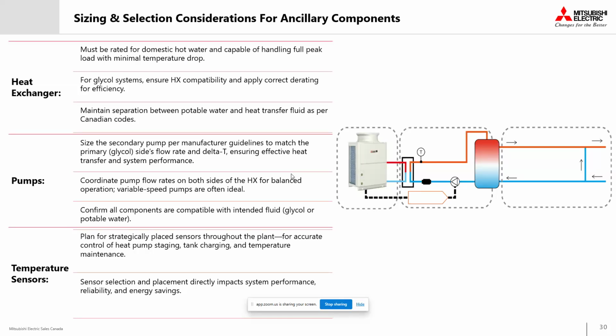Okay, so just looking into some of the key considerations for some of the ancillary components that I just discussed. Each one of these components plays a key role in efficient decarbonized system operation. First, our heat exchangers should be rated for domestic hot water. We need to ensure that they're sized for peak load with minimal temperature drop across that heat exchanger. For systems that are using glycol as a method of freeze protection, we need to make sure that that heat exchanger is compatible and rated for use with glycol, as well as the proper derating factors need to be used when selecting the heat exchanger.